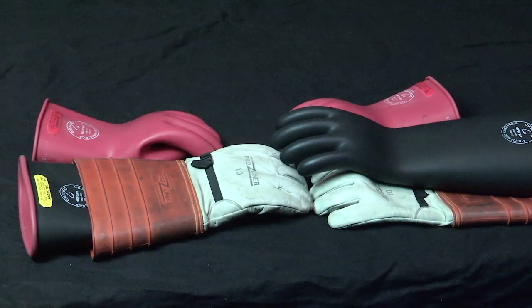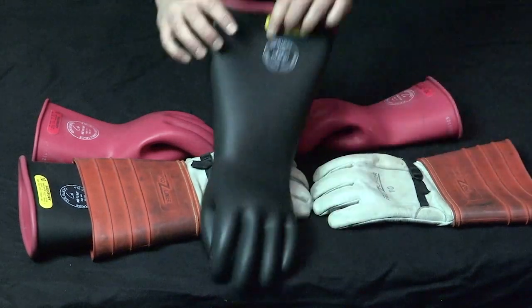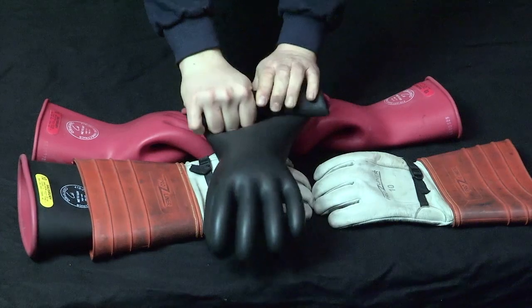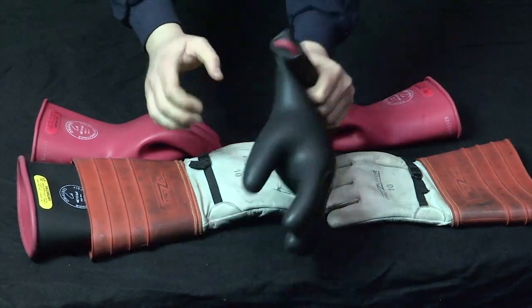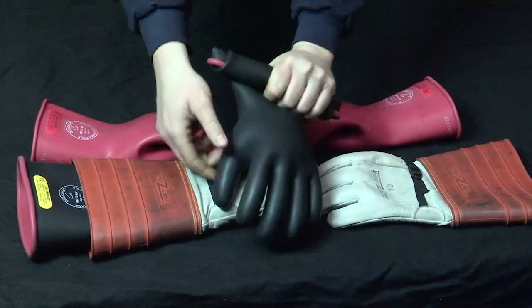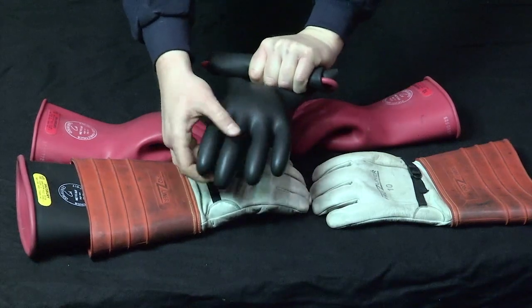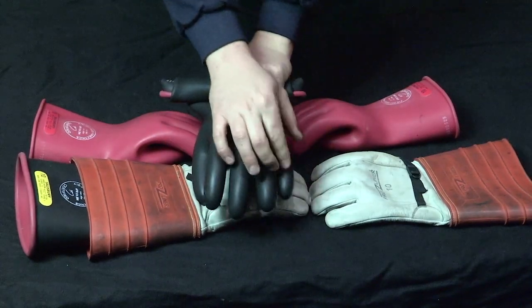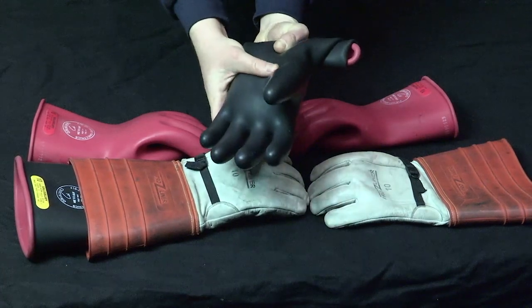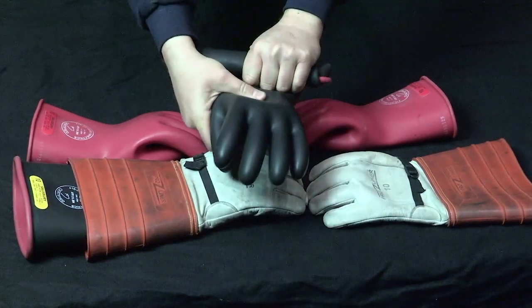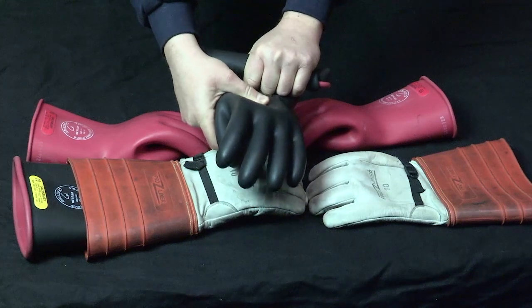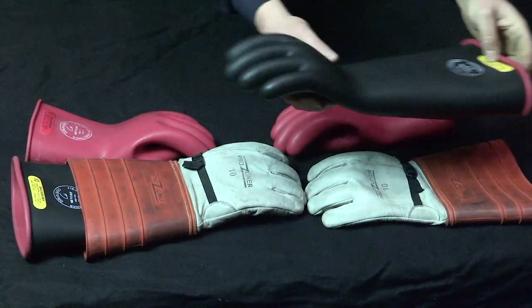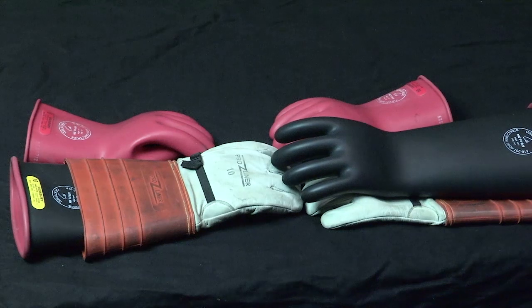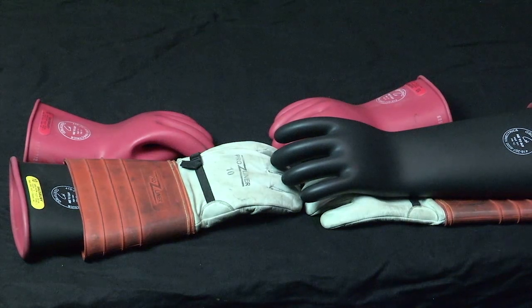An air test tells you if there is a puncture. Twirl the glove to fill it with air and trap it by rolling up the glove cuff. With your free hand, squeeze the glove in various places. This inflation of the glove will amplify any small damaged spots that might not be found by ordinary visual inspection. While the glove is inflated, hold it up to your face to feel or hear if any air is leaking through a puncture. Do not wear rings or watches under your rubber gloves. Electrical research has shown that many gloves have indications of corona cutting where these items contact the gloves.